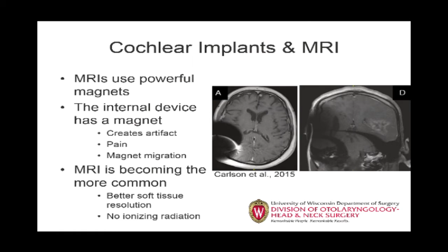There are stipulations. These are called MRI conditional, which means that under certain conditions, an MRI may be able to be obtained. So the MED-EL device, which is depicted here, has a rotatable magnet, which will realign to the magnetic field of the MRI, meaning that the forces imparted are advantageous and don't tend to push on the device. The magnet will spin. Up to 3 Tesla, which is the most common MRI performed today, these devices have been FDA approved. Tesla is a measure of the strength of a magnet. They don't require any special wrapping of the head or special devices. So this can be a good option for patients who may need to have MRIs in the future.